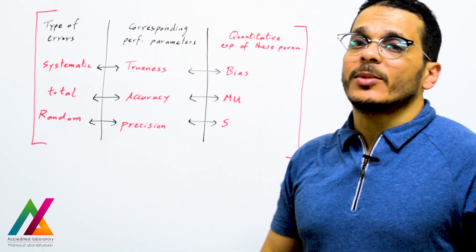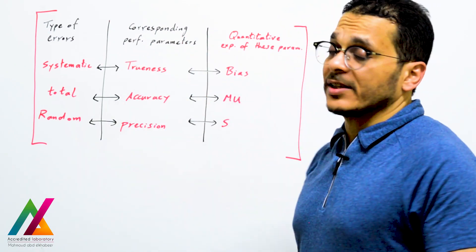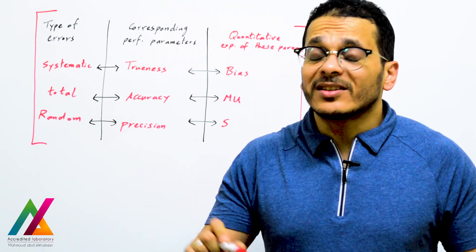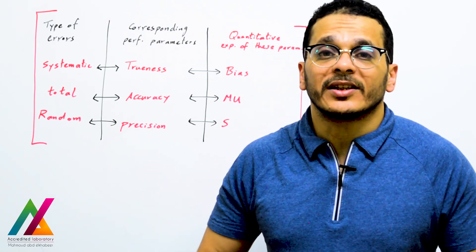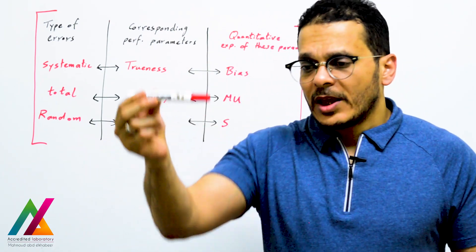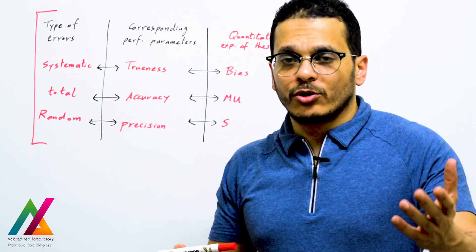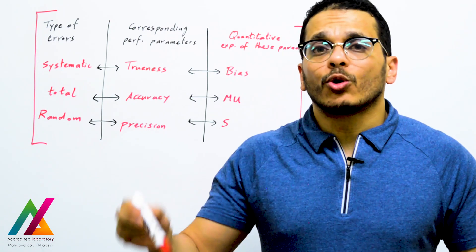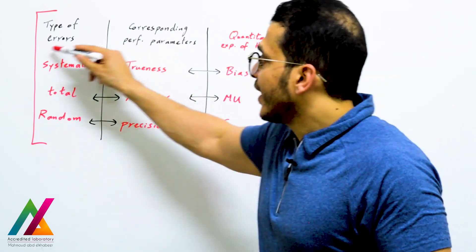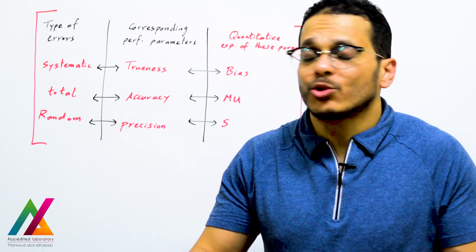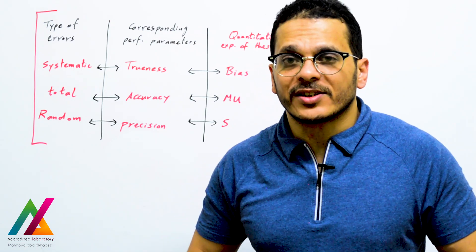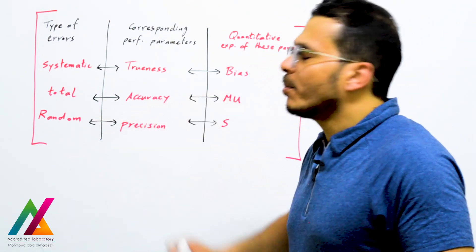Trueness is the estimate of systematic errors and can be expressed as bias. To evaluate trueness, you calculate the bias. Trueness is best evaluated using a certified reference material (CRM) with a known true value. If you perform replicate analyses of a CRM and get results close to the reference value, the average will also be close to the true value, the bias will be low, and you can confirm that systematic errors are low and did not significantly affect your results.